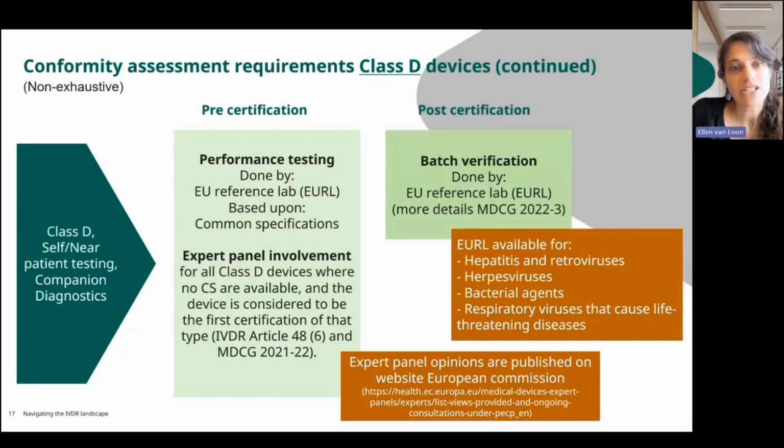And post-certification, batch verification should be done for the Class D devices. And also this is done by these EU reference labs. And more details you can find in MDCG 2022-3.